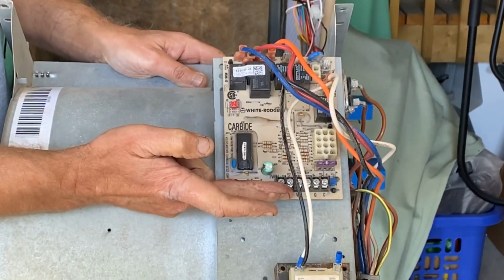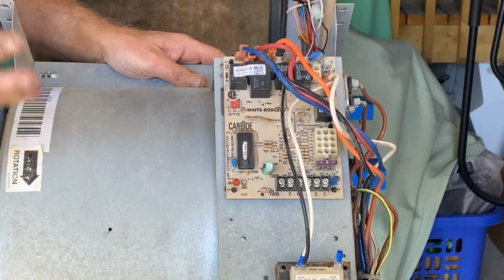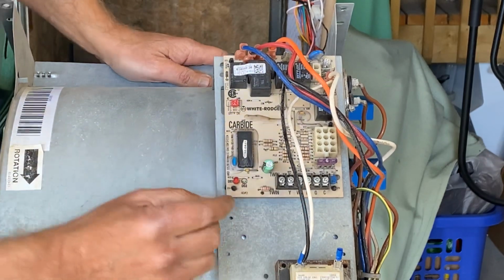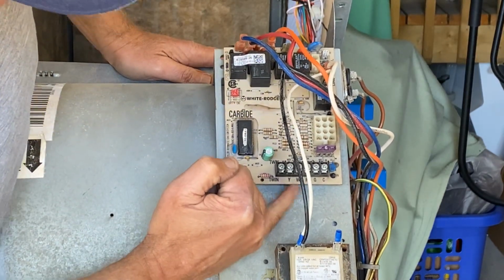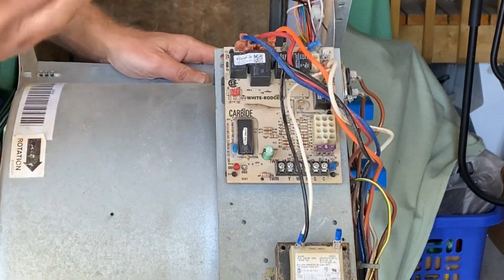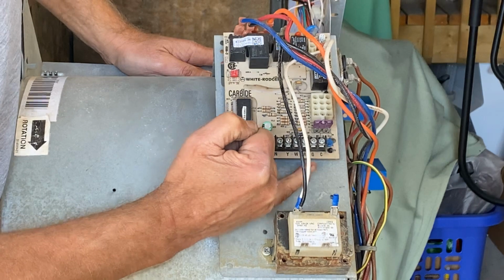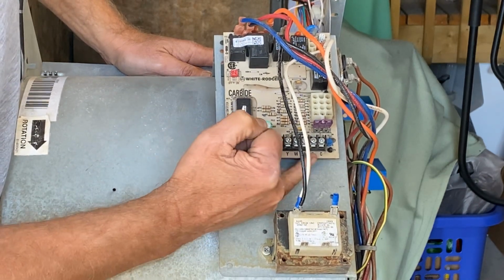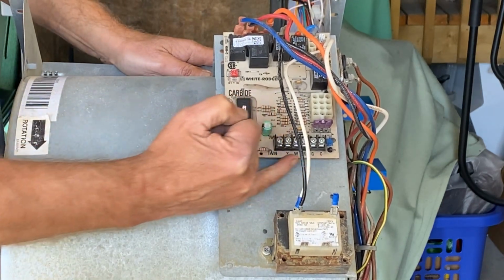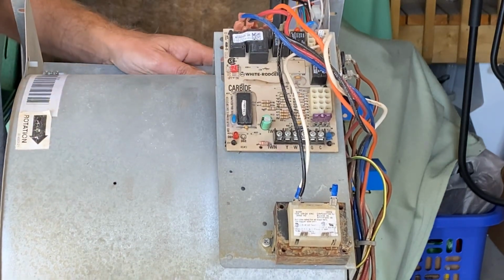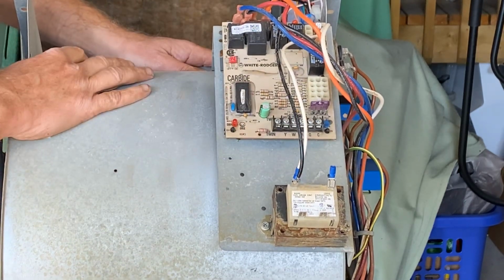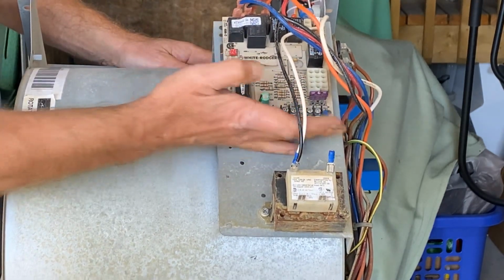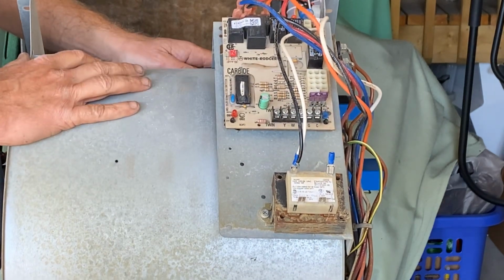The bottom of the circuit board here is my thermostat connections. In electrical class, hopefully you would have gone through the lab on thermostats. You've got a Y terminal, W, R, G, C, so you would know that 24 volt power is R, heating signal is W, cooling signal is Y, fan signal is G, and C is common. Depending on whether you have a programmable thermostat or a mechanical thermostat, that determines what you need to see. That's where your thermostat connections will connect to.